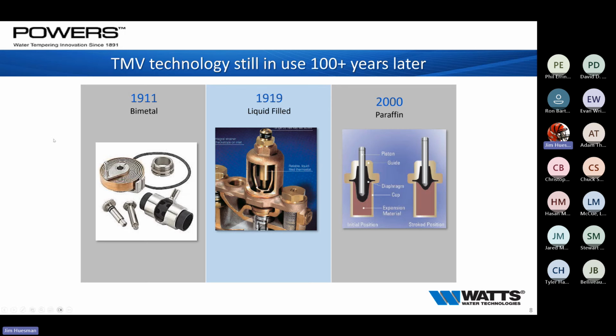Moving away from the bimetals, because it's just not very accurate - it takes a while for that metal to heat up and a while for it to cool down, so it wasn't very accurate. We weren't able to stay within that code of plus or minus 7 degrees. As we spoke about, our temperature has to be there, because if I need my water at 120 and I have a 7-degree plus or minus, well 120 to 127 - that 7 degrees results in, hey, this is way too hot, and you will notice a 7-degree difference. As we moved up in technology, we started doing more of a gas or liquid filled design.